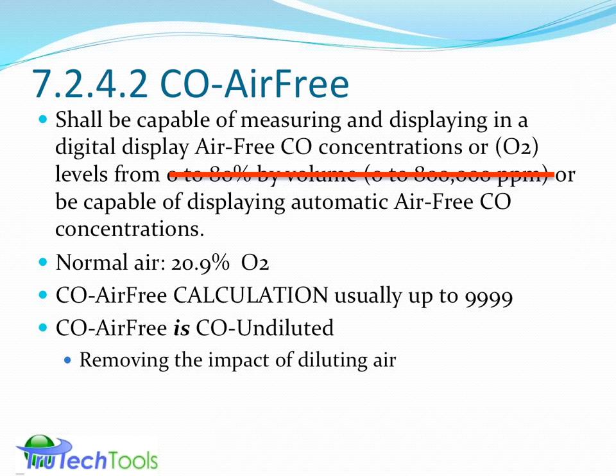One factor I do want to mention here is to make sure the words undiluted or diluted sample mean something different than the calculation CO undiluted. That's got to be made clear. Usually we're looking at making measurements in an airstream that's undiluted, meaning before any kind of draft diverter. So that's one notion. The other notion is an undiluted calculation, where it removes the diluting elements from it. So don't confuse an undiluted measurement with a CO undiluted calculation. Probably have to work a little bit more on that. We actually have another webinar strictly on CO air-free where we slow down and break this down a little bit further. It does also qualify for 1 BPI CEU if you watch it live. So that's also available. I'll show you that on our webinar calendar before we leave the session today.